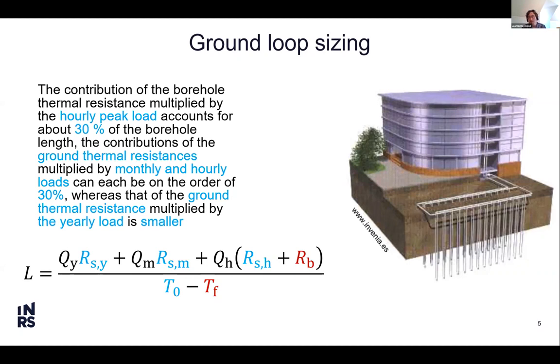While in cooling mode, it's the contrary, right? The warmer is the fluid, the less efficient. So you have to decide the good balance, right? And have a good fluid temperature in your system that provides energy savings, but that does not increase too much your length, because if the length is too long, then the system is just too expensive to install. So designing a system is really to find a good balance with what the ground can give you to fulfill the building energy needs, taking into account what you can change in your design to have more performance from your borehole with the borehole thermal resistance.